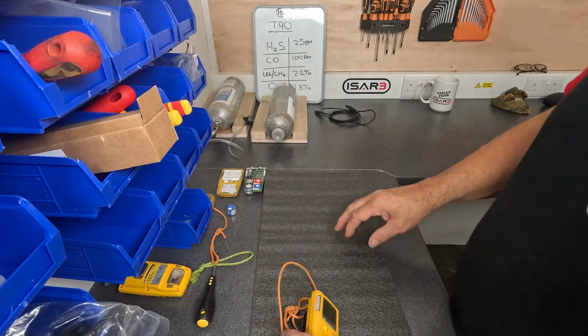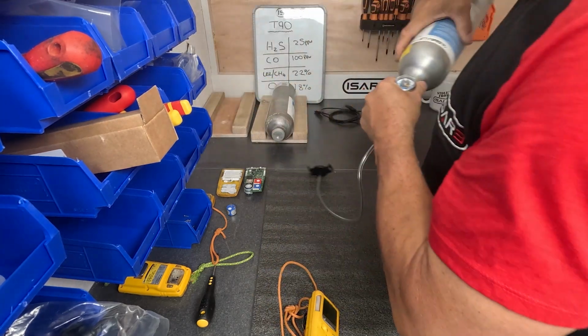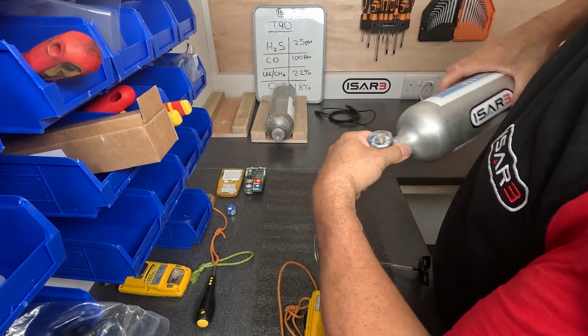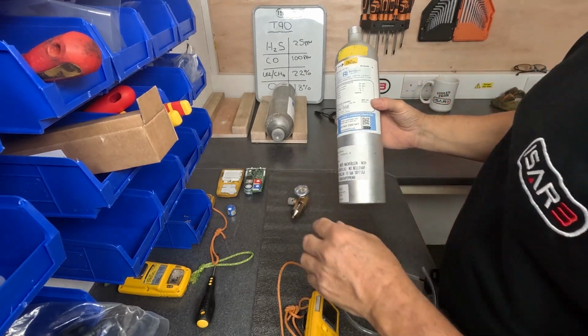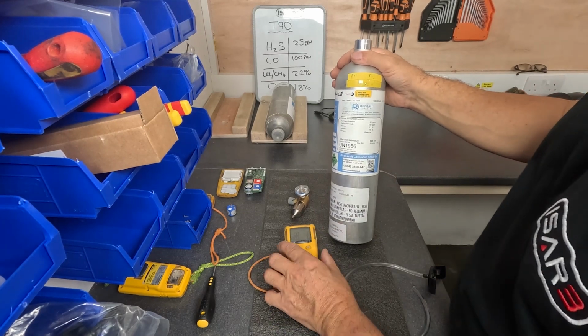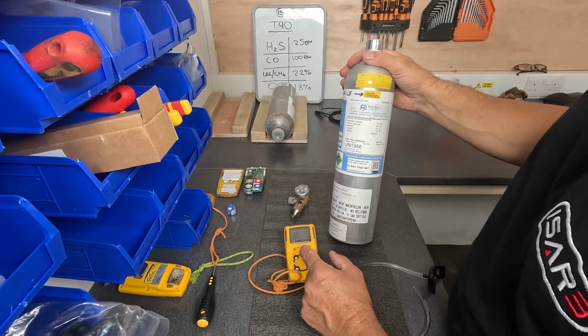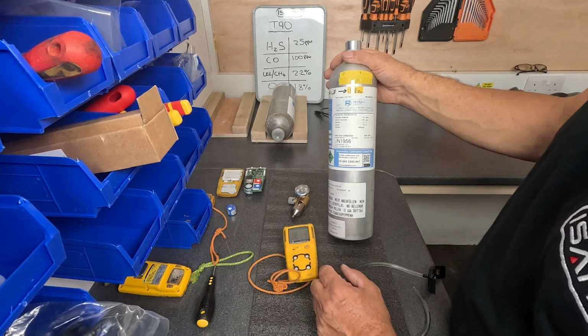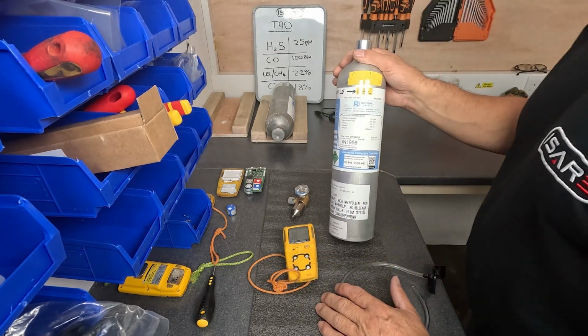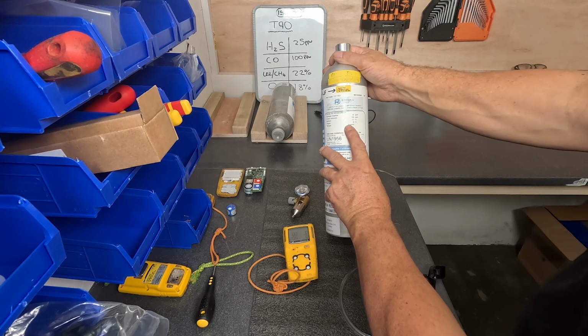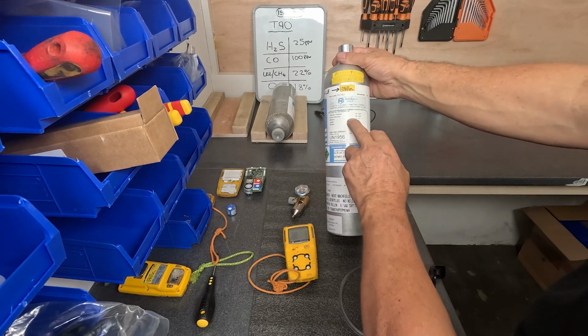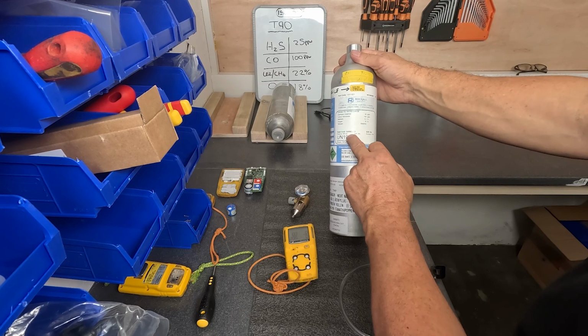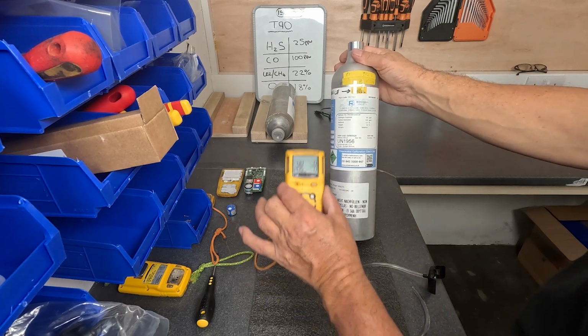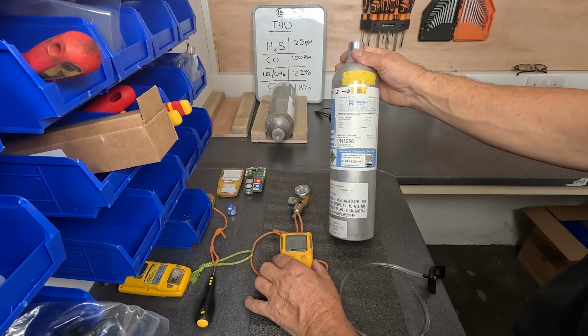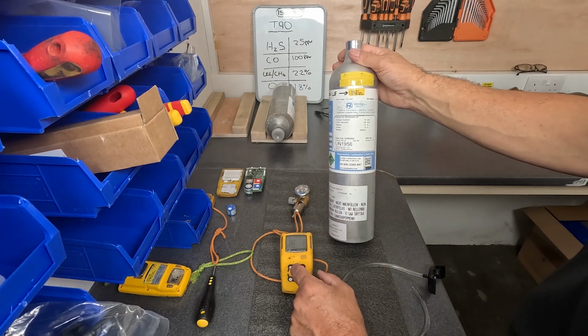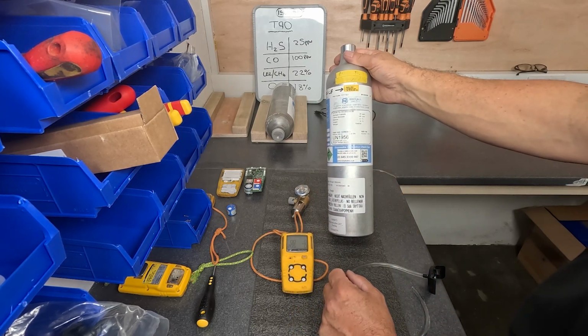To do the bump test, you will need a calibration gas that is set up for your particular gas detector. You just talk to your supplier, unless you've got the software to go in and find out what this gas detector is set to, and they will then tell you which, or supply to you, a quad gas so that you can do all four sensors at once. We've just used Rockall here, a local supplier to us, to provide a quad gas that's set up and has the same concentrations of gas in here as the set points for the calibration on here. You can find that from the software.